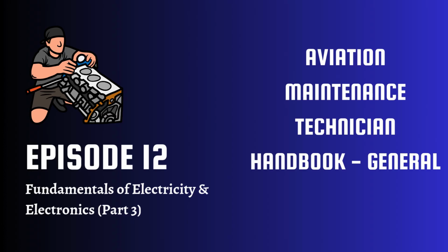Makes sense. Then there's compound wound. Compound wound uses both a series field winding and a shunt field winding on the same poles. Best of both worlds. Kind of. Usually they are cumulative compound, meaning the series field's magnetism adds to the shunt field's magnetism. The series field provides some boost as the load increases, which helps counteract the voltage drop from armature resistance and armature reaction. So it gives better voltage regulation. Much better, especially under varying loads. Depending on the strength of the series winding, you can get flat compounding, voltage stays constant, under compounding, slight drop, or over compounding, the voltage actually rises slightly with load. Used where stable voltage is really critical.